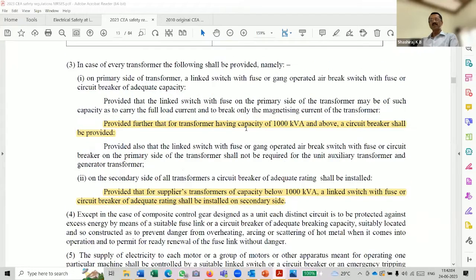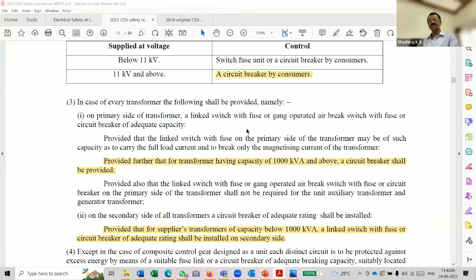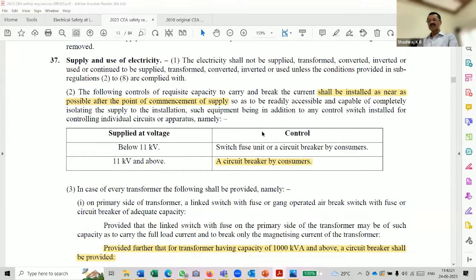But now we have made it mandatory for all 66 kV or 33 kV, and of course the KPTCL transmission companies with 110, 220 and 400, to get their drawings approved by the electrical inspectorate, similar to the consumer who gets his HT installation approved by us. They also have to get it approved and provide the breaker.